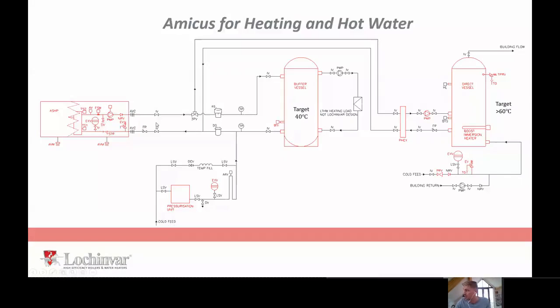But what you get is 2 temperature sensors. You have a heating sensor, you have a hot water sensor. Under normal circumstances, your heat pump's job in life is schematic number one. It's to maintain a thermal store at a temperature so you can flow off to your various zones, serve a heating system, and satisfy the user and keep them warm on your nice cold winter's days. And then it will auto monitor this BTS sensor, so the sanitary hot water sensor. And when it notices that that temperature has dropped below 60, it will switch alive from its control panel, turn a motorized three-port valve, increase its flow temperature to 63 degrees centigrade, flow into the plate heat exchanger at 63, return at 58. The secondary pump comes on briefly after that, taking our water back up to over 60 in the top 2/3 of this vessel to distribute off to the building. When it's satisfied that this vessel's now back up to 60, it will drop the live to the three-port valve, change its expectation on flow temperature, and go back to serving our heating system.